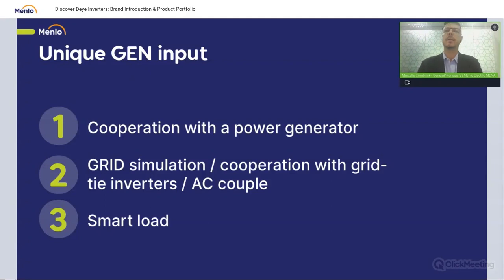Something quite unique to Deye is the unique genset input. There are three scenarios, but you can only choose one. You can't do all three at the same time. First scenario, the standard scenario, cooperating with a power generator. Second scenario, grid simulation, cooperation with grid-tied inverters, AC coupling, which we discussed in previous slides also. And then the third scenario is a smart load, and I'll explain what the smart load is. Next slide, please.